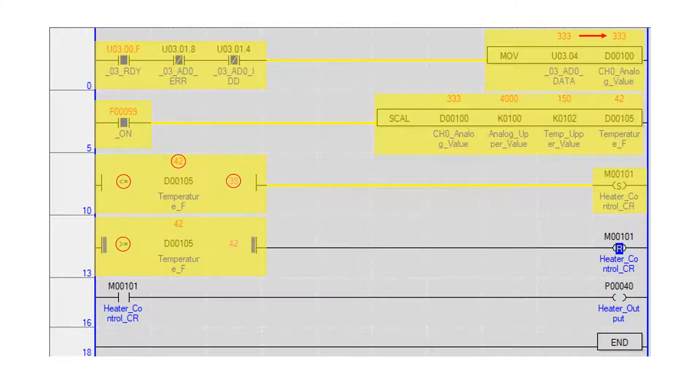Using a greater than or equal to compare instruction, the current temperature is compared to a set point of 42. If the temperature is at or above 42 degrees, the internal bit heater control CR is reset. The heater control CR bit turns the discrete output heater output on or off.